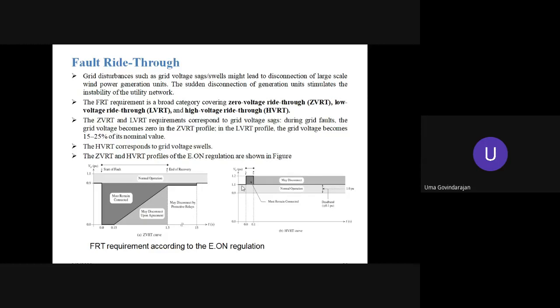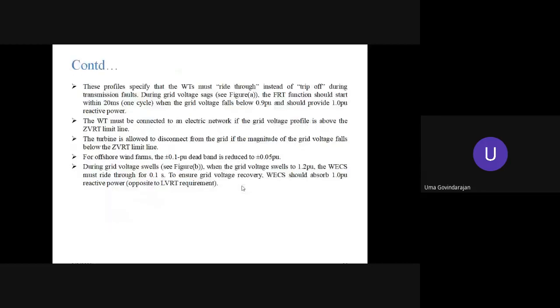Okay, so one has to know about LVRT, or fault ride-through requirement, according to the international regulation. Different countries have different regulations. These profiles specify that wind turbines must ride through. That's very important. They must ride through, must stay connected instead of tripping off, instead of coming out of the grid. It should stay connected during transmission faults.